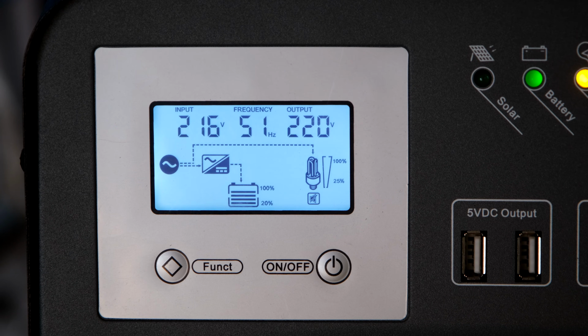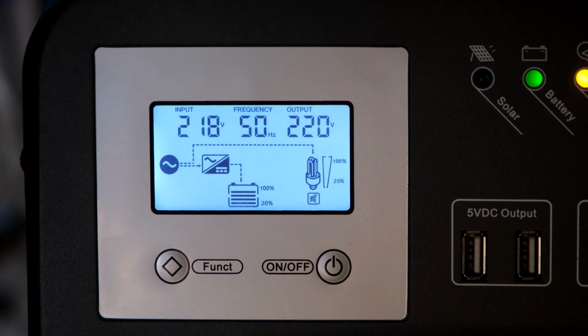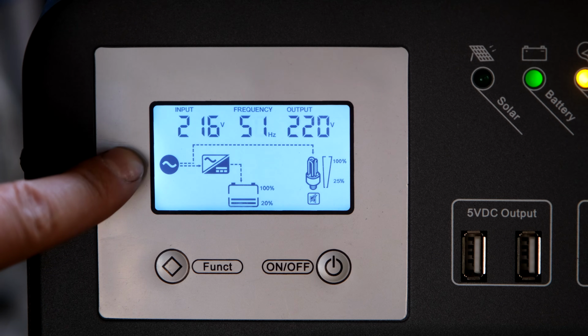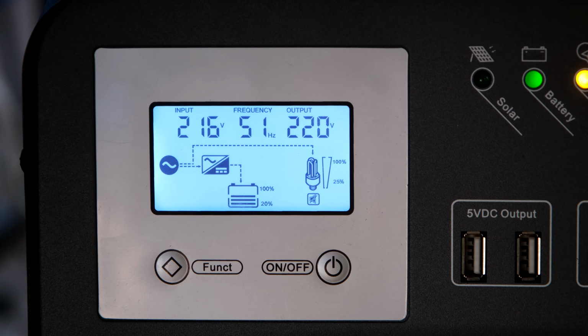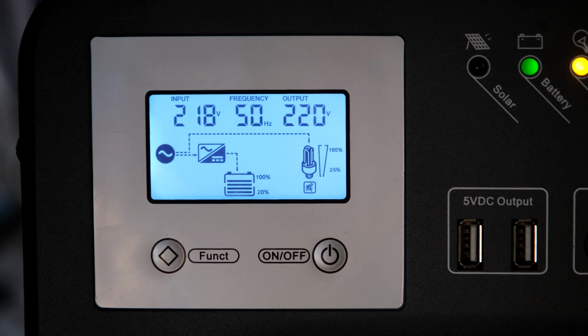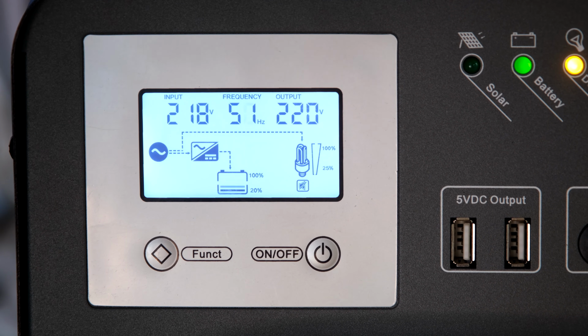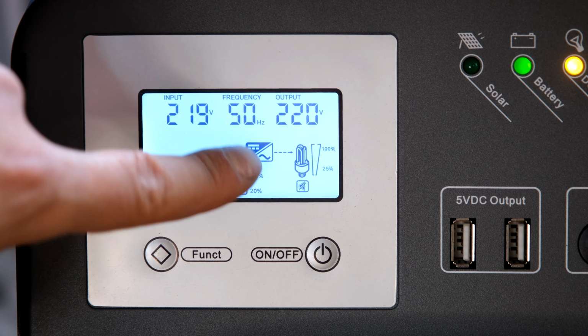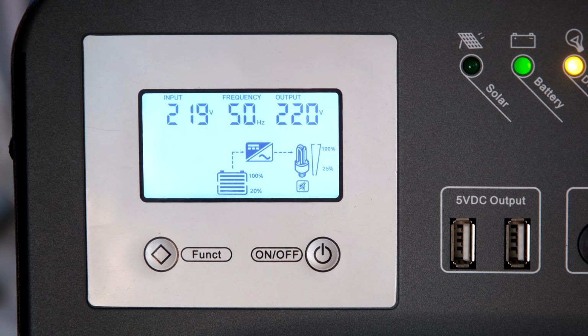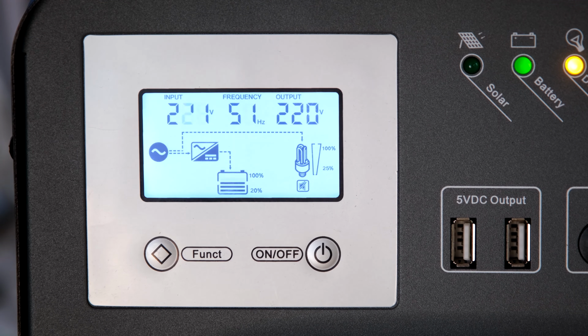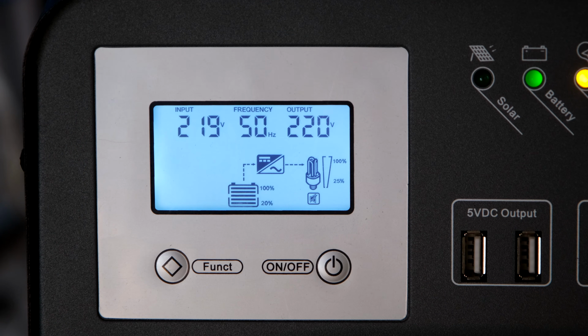And that is not good for the load because it is switching over the load constantly. Remember earlier I showed the floodlight being changed over and how there were moments where it went dark or it flickered. That is not good for our loads. Now, this is not necessarily a problem only on this unit. This is a problem with most line interactive UPSs and inverters. So I'm not specifically criticizing this product. What I'm saying is that if you are going to be using the product with a generator, maybe consider first using an online UPS to clean the power before being fed into the RCT inverter, which is true for most line interactive UPSs.